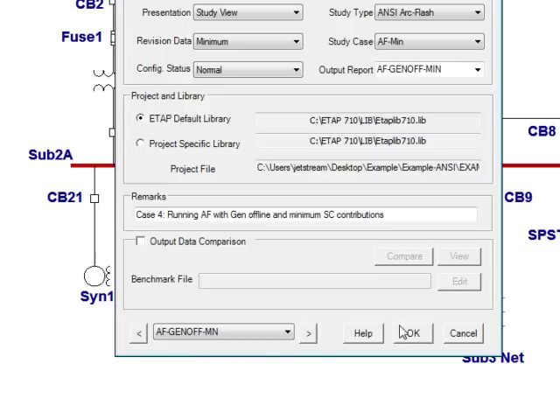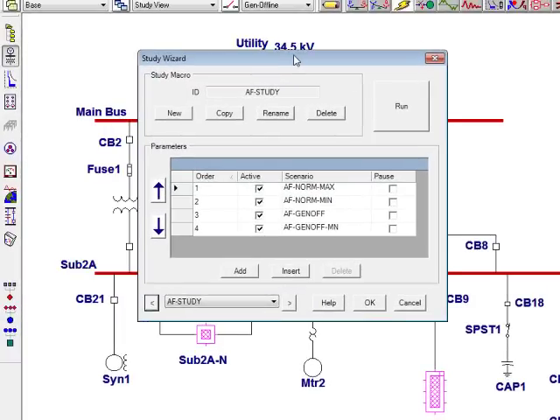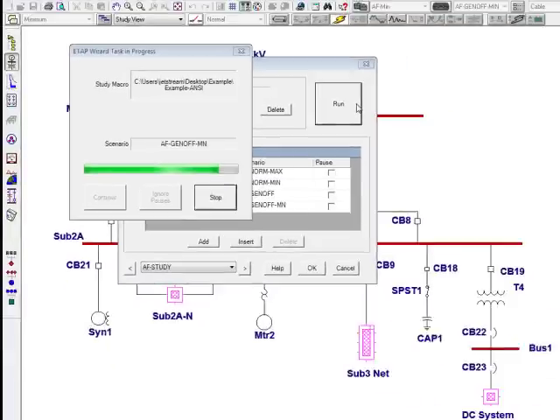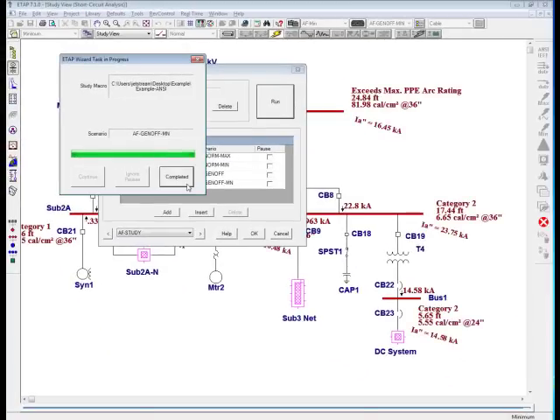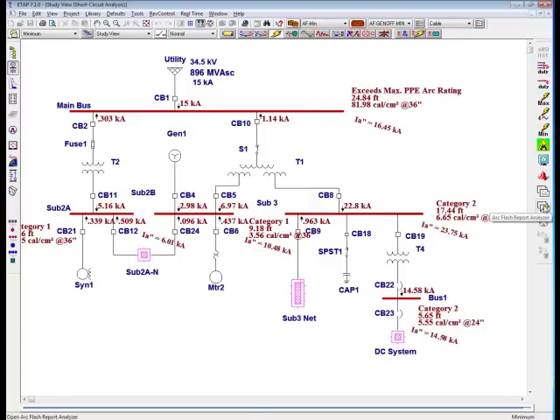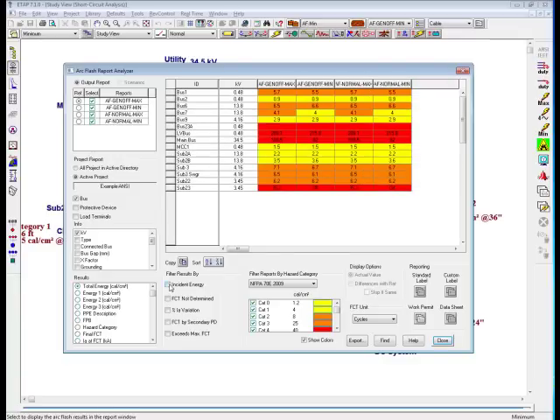So instead of running each scenario individually, I'm going to go ahead and utilize the study wizard, which is the button directly below the scenario wizard. I'm going to go ahead and run my study, and notice that all four cases are run within a click of a button. Once that has been completed, I'm going to select OK and navigate to the ArcFlash report analyzer. From there, I've noticed that all my reports have been created based on my four cases that I've run. These are the individual results for each case and the results for all the buses.